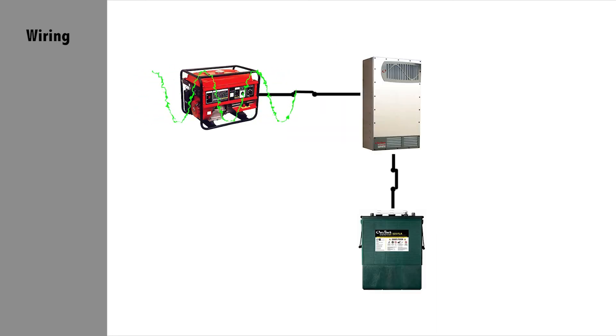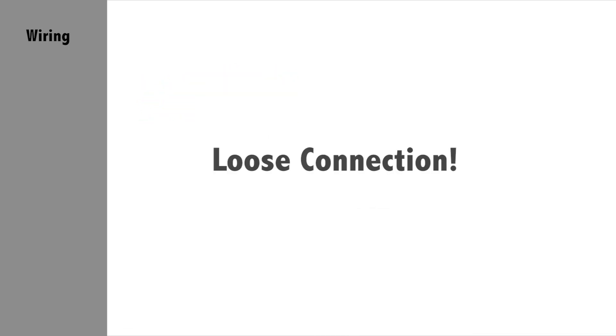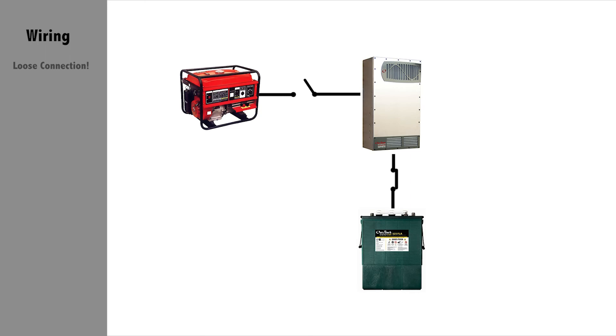Okay, as stated before, if the output power of the generator is fluctuating or drops under load and possibly even goes outside the acceptable voltage and frequency range of the inverter making a disconnect, this may be caused by a loose connection. Check all AC connections starting from the generator and work yourself downstream to the Outback system. Retorque as needed.